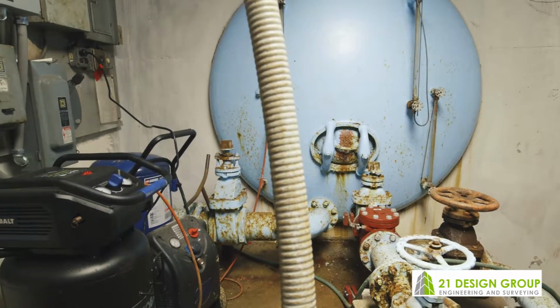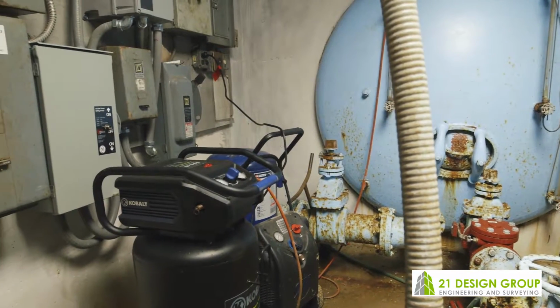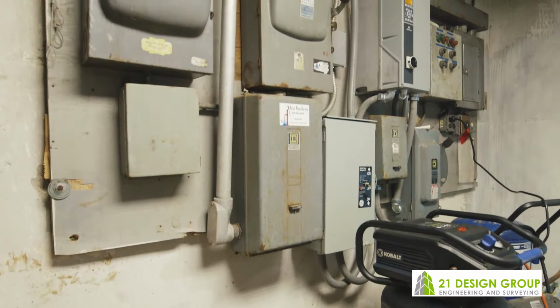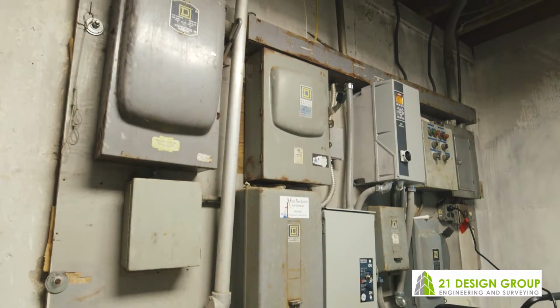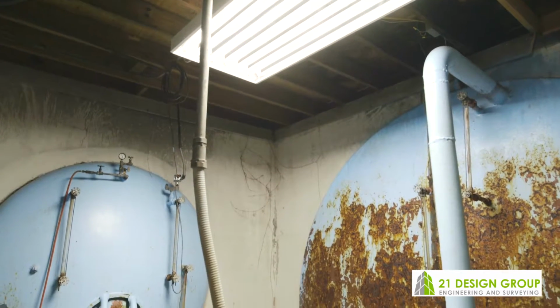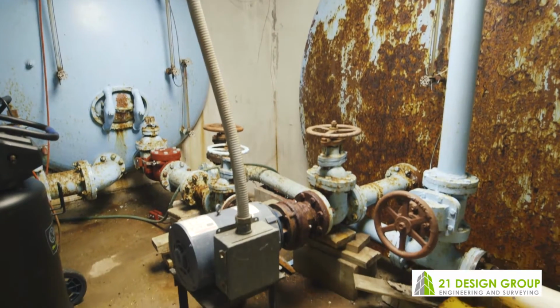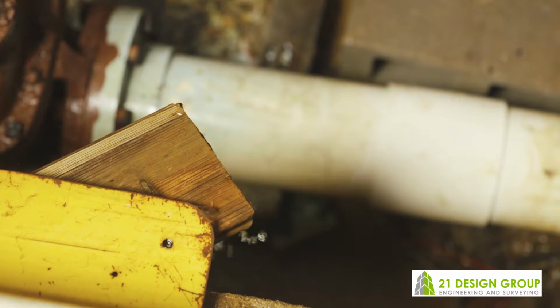The well house's lack of a backup generator and backup booster pump leaves the entire system vulnerable to total water loss should the already undersized booster pump fail. The house's 25,000-gallon total water storage is significantly insufficient, with average summer daily usage approaching 200,000 gallons. In the case of a breakdown, residents would run out of the system's water storage in only 2.5 hours. As is, many residents are regularly left with no water on weekends and holidays during peak summer hours.